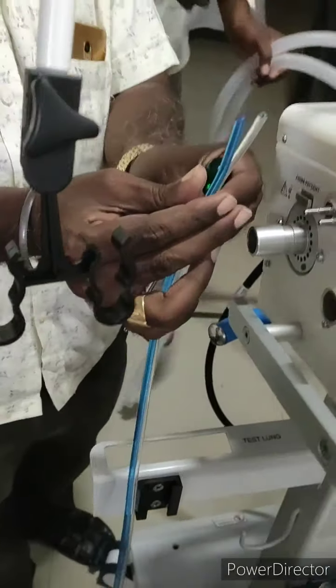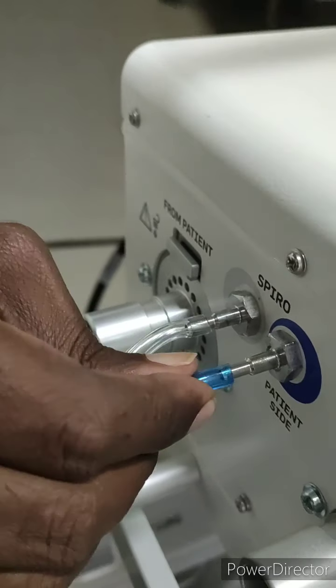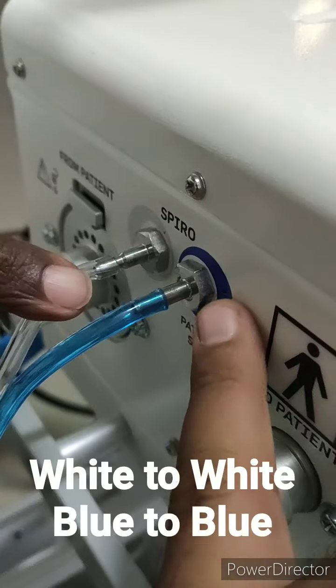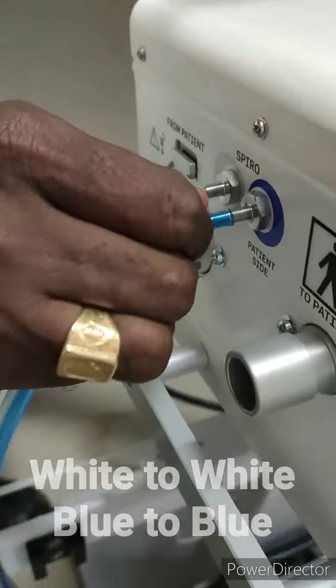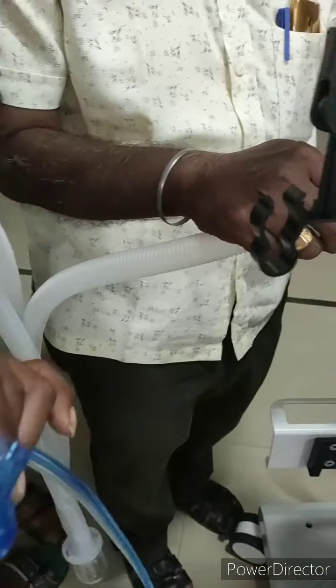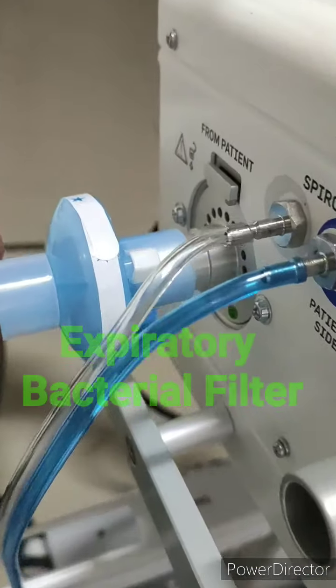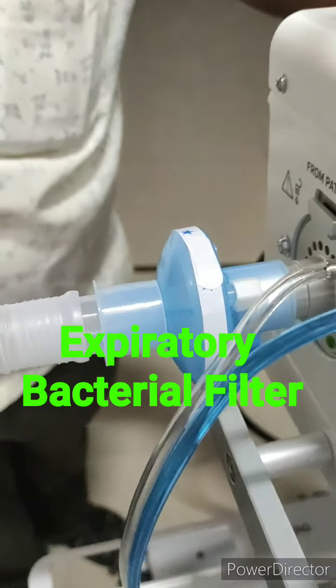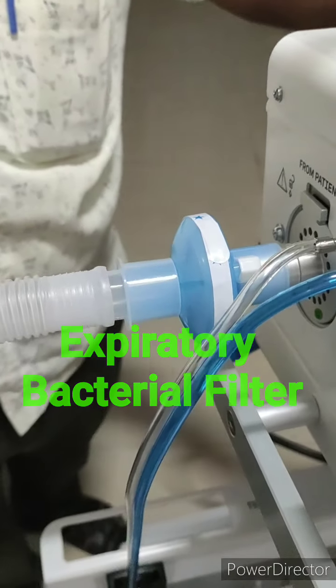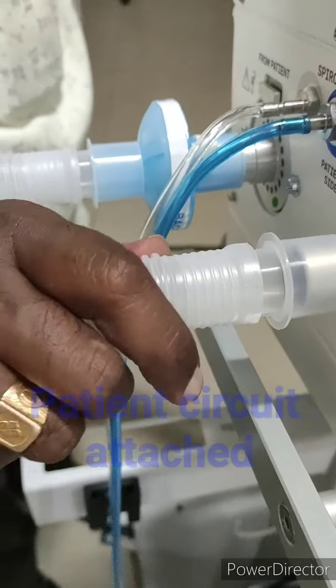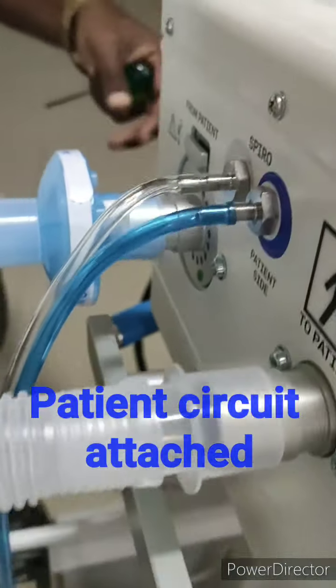First we need to attach this flow sensor. White should be attached to white, and blue should be attached to the one with blue circle. Okay, and then we connect the HME filter. Okay, and this is coming from patient, so we have to attach a bacterial filter here, which is supplied with the circuit. This is a disposable circuit. Okay, so we have attached the circuit to the ventilator.